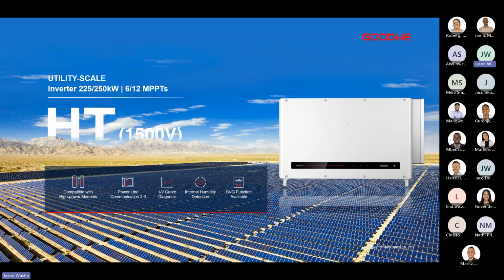Ranging from 6 MPPTs in 3 strings or 12 MPPTs in 2 strings, for either model, with 30 and 60 amp per MPPT, max 50 and 90 short circuit. Like I said, you can have quite a massive number of panels per string to generate quite a lot of blue green energy. Now, with its operating MPPT voltage ranging from 500 to 1,500 volts, you will not go wrong with the HT series.